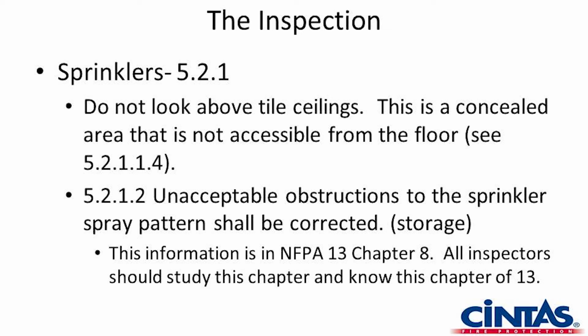Unacceptable obstruction to the spray. Usually we're talking about storage, whether it be a walk-in cooler or freezer, or a storage room where things get stacked too high. We need storage to stay at least 18 inches below a standard sprinkler, so that the water pattern we've been talking about, that umbrella effect, has time to develop without hitting an obstruction.